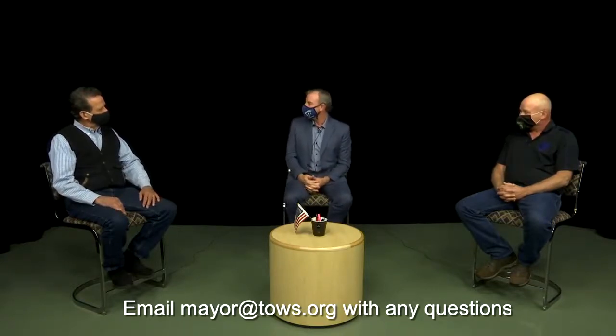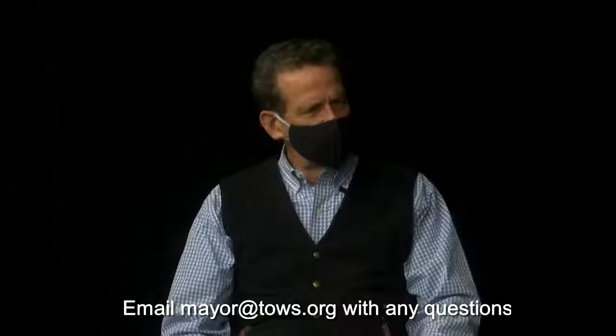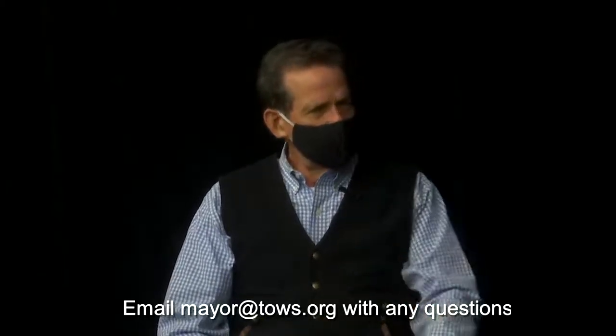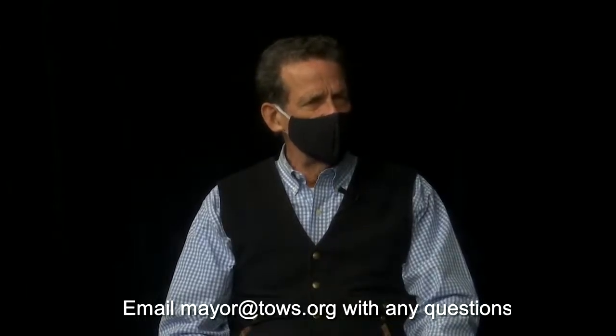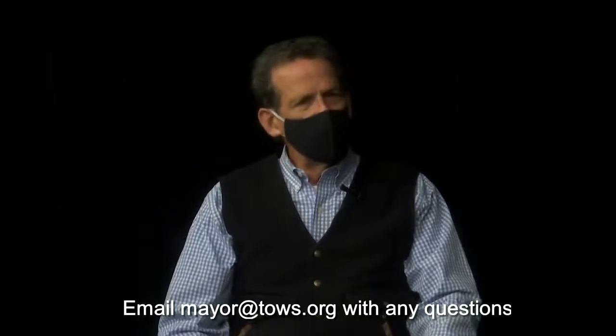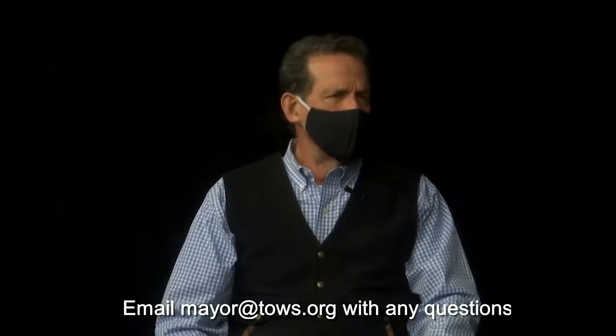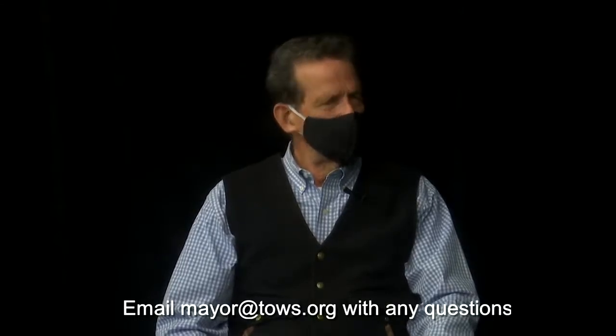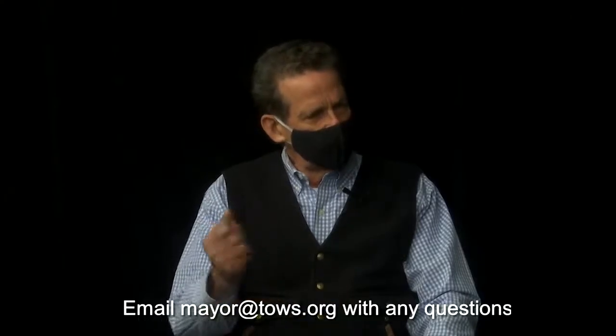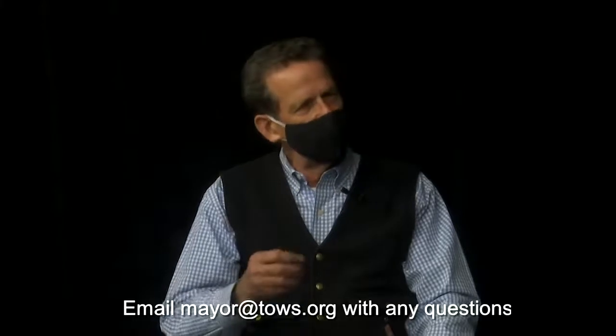So what's the process? I went to representative schools and representative systems within those schools. What Scott asked me to do was to see what the available CFM rating was for the various rooms. CFM stands for cubic feet per minute of air. The idea was to determine what kind of CFM capacity we have through the filter. The HVAC system brings air from the living space or occupied space, takes it through the filter, and then brings it back to the room, having been filtered at a particular level of particulate size. Very important.